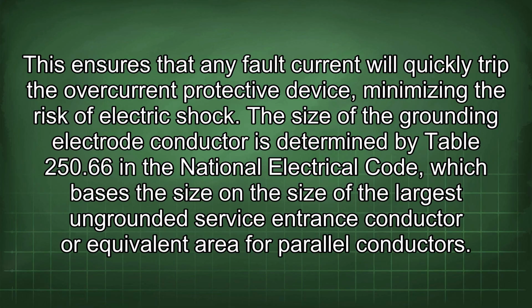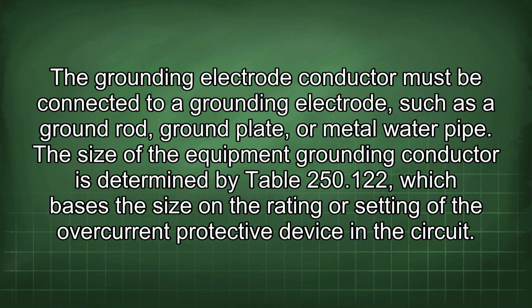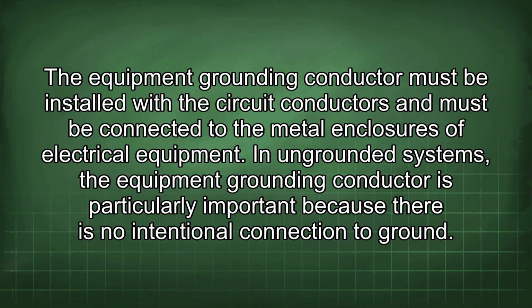The size of the grounding electrode conductor is determined by Table 250.66 in the National Electrical Code, which bases the size on the size of the largest ungrounded service entrance conductor or equivalent area for parallel conductors. The grounding electrode conductor must be connected to a grounding electrode, such as a ground rod, ground plate, or metal water pipe. The size of the equipment grounding conductor is determined by Table 250.122, which bases the size on the rating or setting of the overcurrent protective device in the circuit.